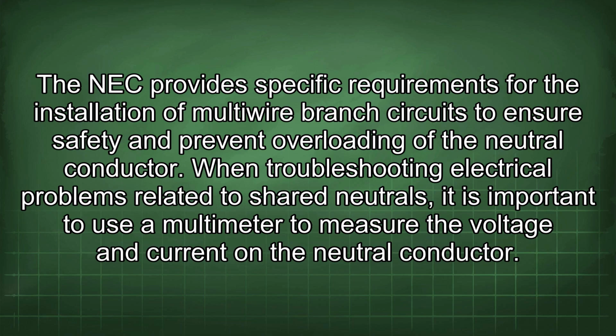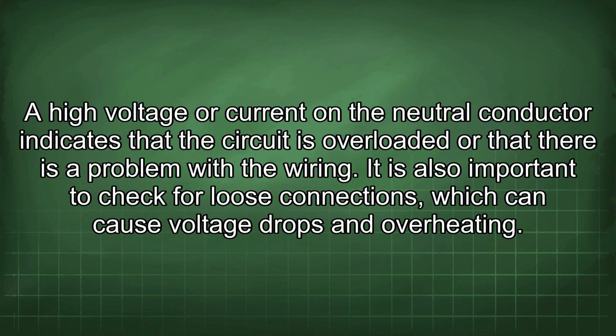When troubleshooting electrical problems related to shared neutrals, it is important to use a multimeter to measure the voltage and current on the neutral conductor. A high voltage or current in the neutral conductor indicates that the circuit is overloaded or that there is a problem with the wiring. It is also important to check for loose connections, which can cause voltage drops and overheating.